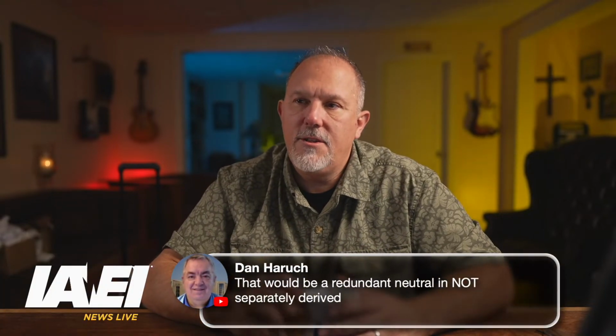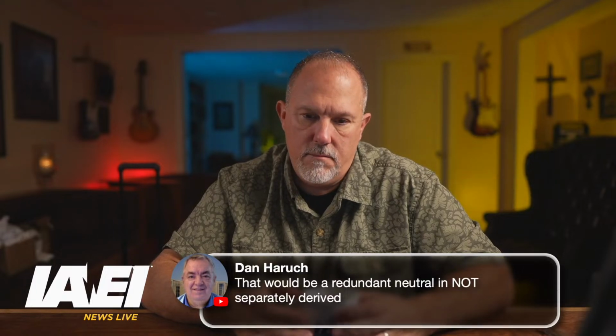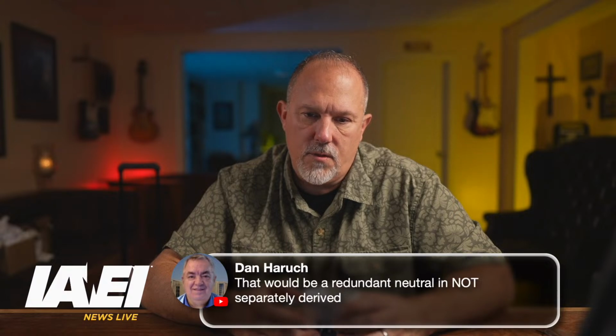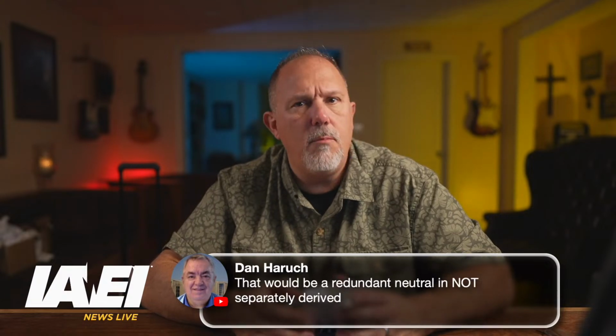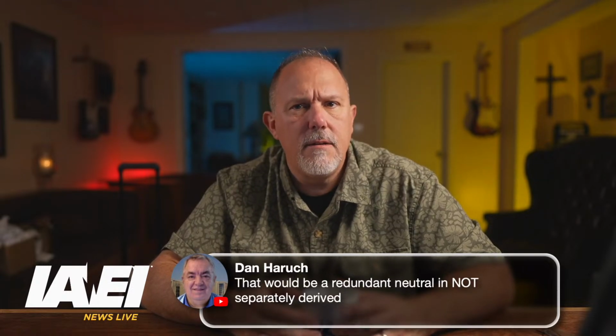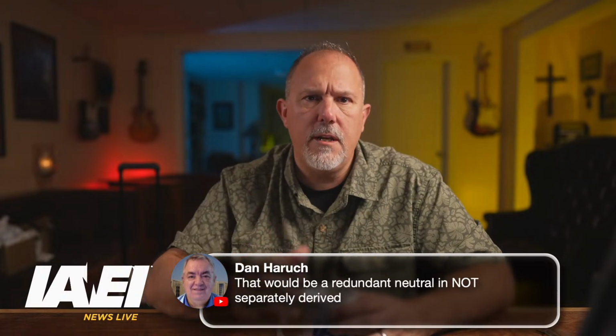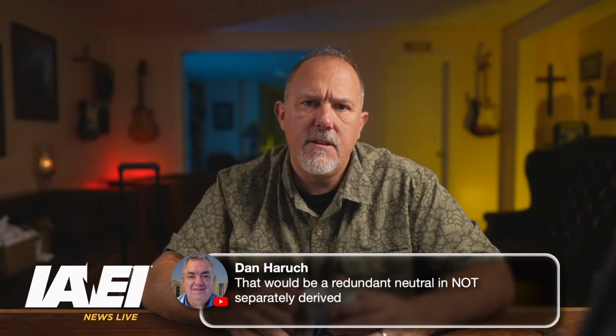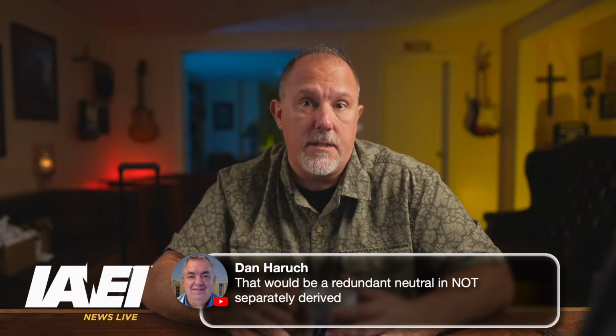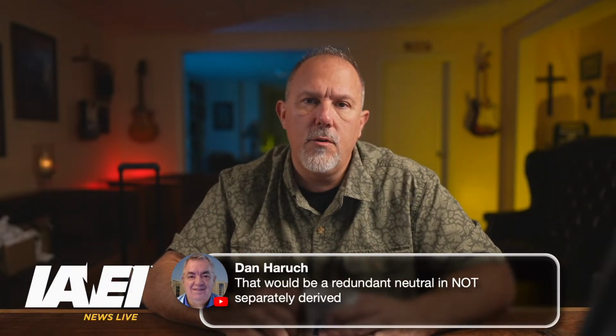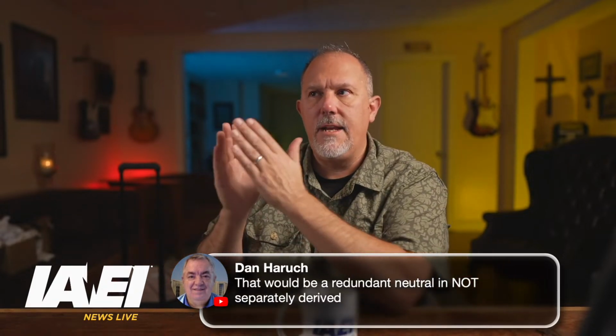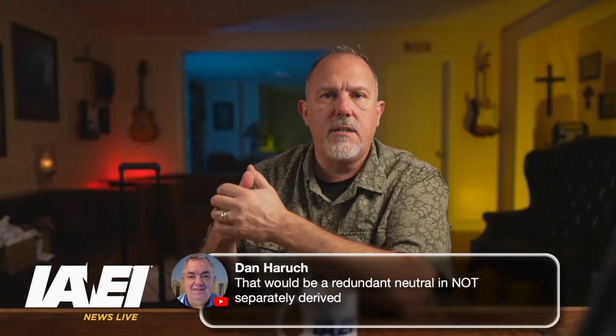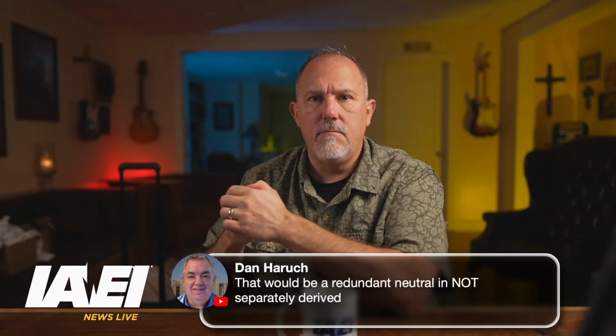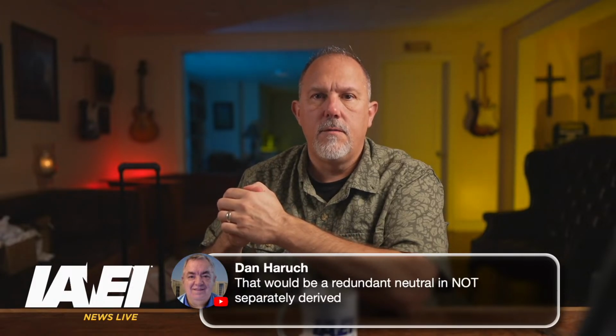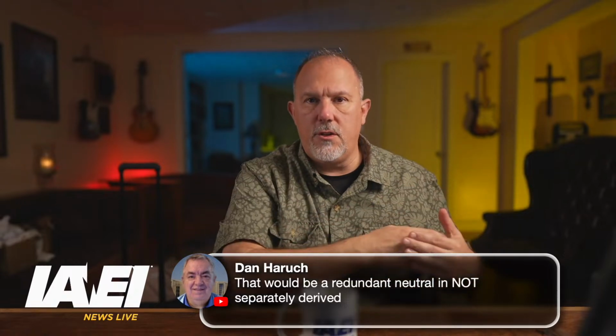Different article, different day. That would be a redundant neutral in a non-separately derived system. In a non-separately derived system, you don't bond the neutral and the equipment grounding. So all you're doing is bonding the equipment. So it's not a neutral. It's not a grounded conductor. It's a grounding conductor. It's a bonding conductor. Your neutral that's coming from the generator is not connected in the generator and bonded to the equipment. It's floating. It's isolated from the equipment. The bonding is all occurring in your service equipment.